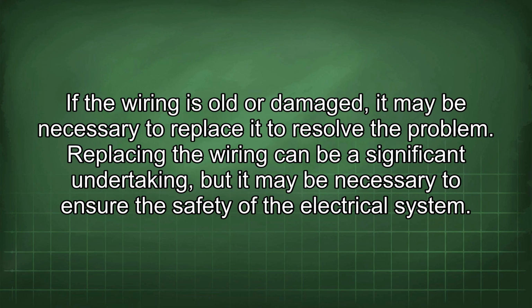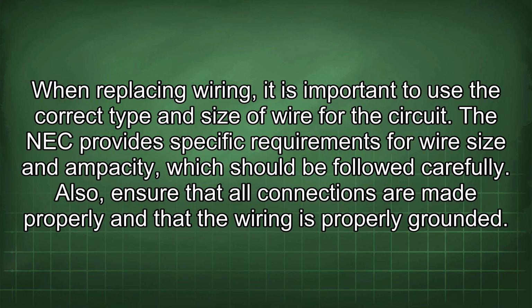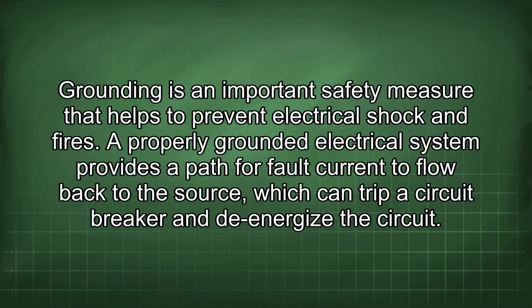Replacing the wiring can be a significant undertaking, but it may be necessary to ensure the safety of the electrical system. When replacing wiring, it is important to use the correct type and size of wire for the circuit. The NEC provides specific requirements for wire size and ampacity, which should be followed carefully. Also, ensure that all connections are made properly and that the wiring is properly grounded. Grounding is an important safety measure that helps to prevent electrical shock and fires. A properly grounded electrical system provides a path for fault current to flow back to the source, which can trip a circuit breaker and de-energize the circuit.